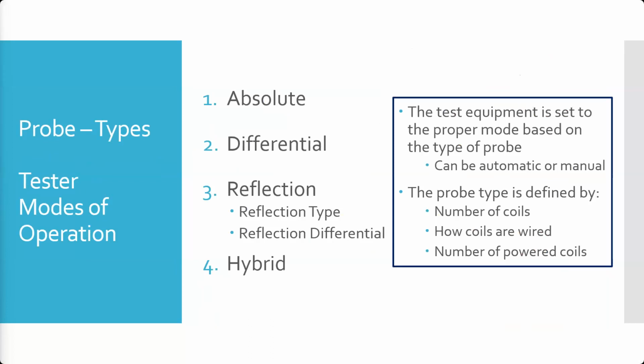Okay, so manual, most are manual. Some of the real high-end stuff coming out in the last few years is automatic, where the probe and the device can talk to each other. And then for the probe type, you have things like the number of coils, the number of turns of wire, how big they are, and then whether your coils are powered or not. Sometimes you can run power to the coils. Sometimes there's passive coils that are doing more listening. Sometimes there's coils that are more amplified than others, right? There's all kinds of configurations that can be done inside to try to get different results or to try to see different things.